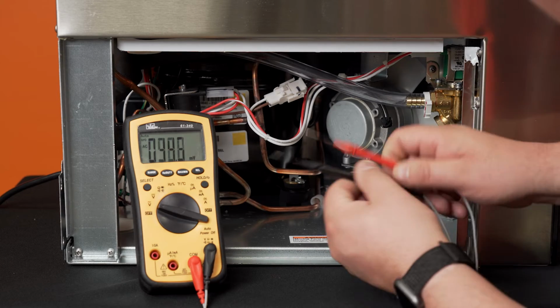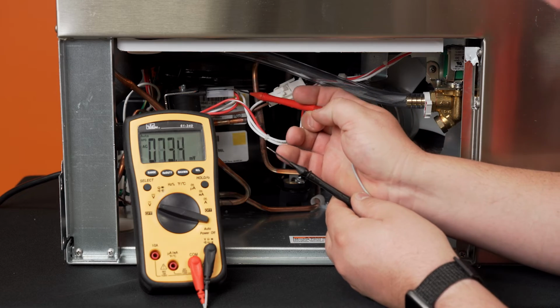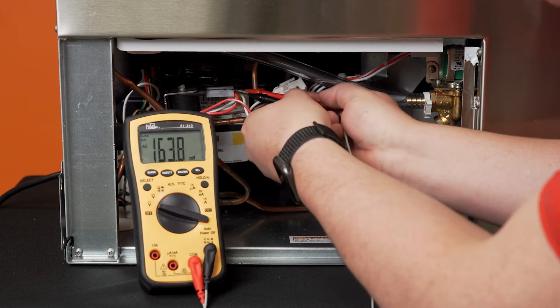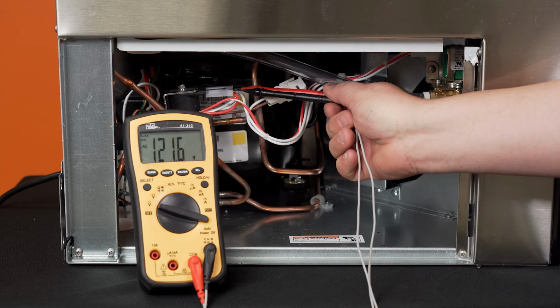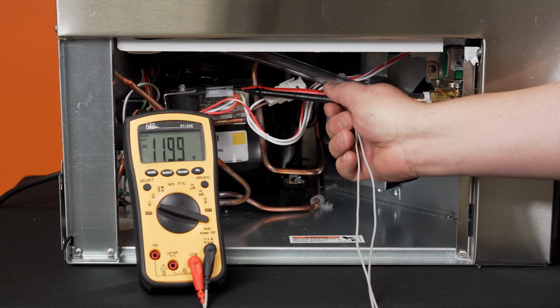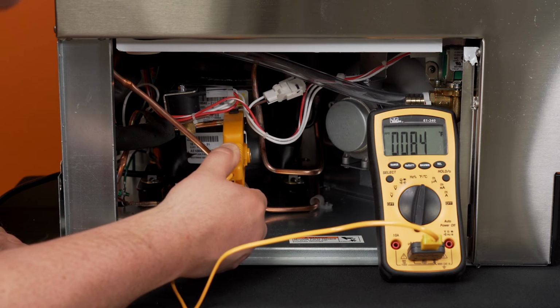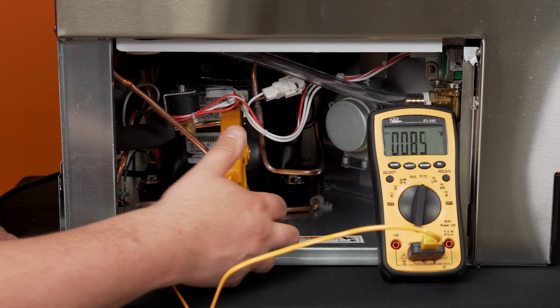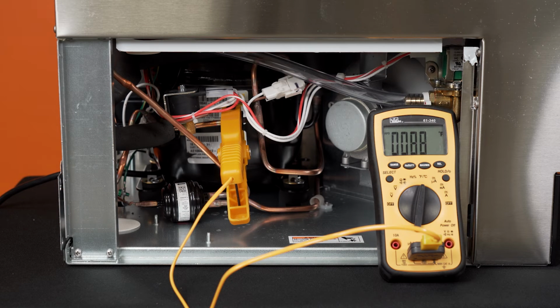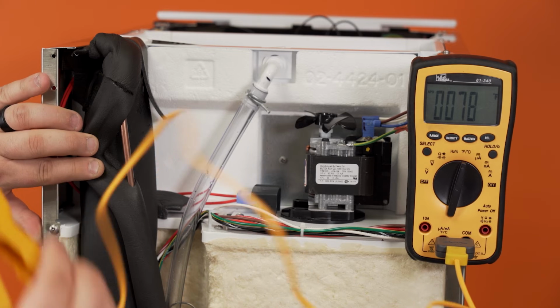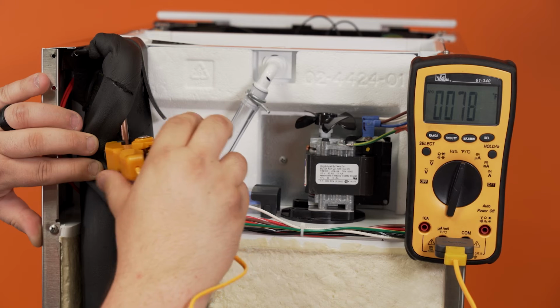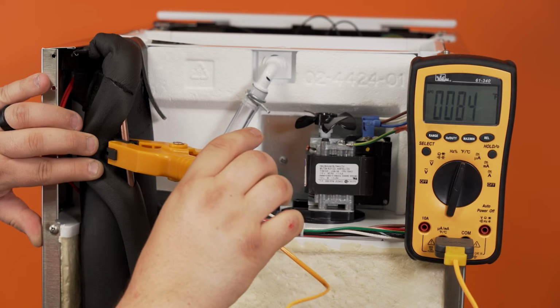Using a multimeter, confirm the hot gas valve has power. If no power is found at the valve, check for power at the control board. If no power is found, replace the control board. With the temperature probe or clamp, take a temperature reading on the copper tubing on either side of the hot gas valve.